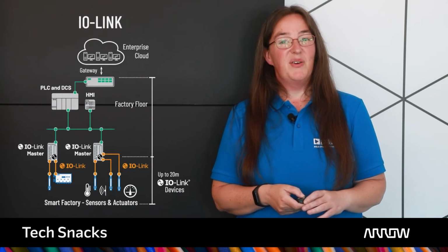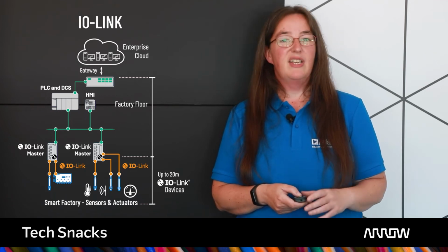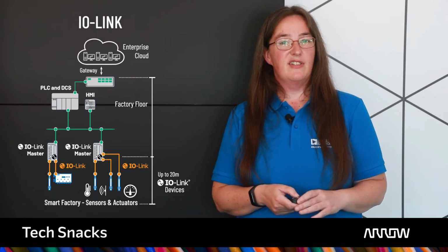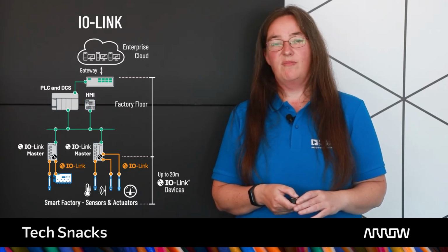Let's consider the factory floor. Historically, data transfer from basic factory sensors to a controller was unidirectional, from the sensor to the master only, requiring a technician to physically intervene to make configuration changes. To make a real-time, reconfigurable factory floor a reality, a better solution was needed. Enter IO-Link. IO-Link is a short-distance, bidirectional, digital, point-to-point industrial communication networking standard, enabling remote configuration, communication, and diagnostics.